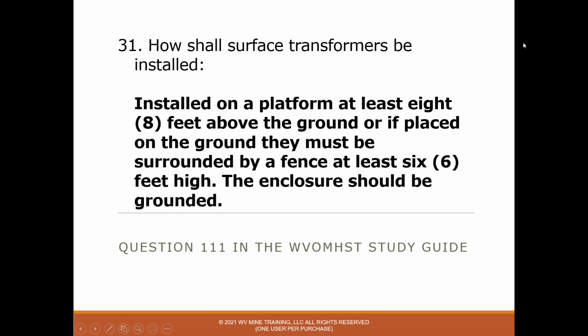Someone's told me this question is definitely on the test, and what they're looking for is the numbers. So if I have a surface transformer, I basically have a choice. I can put it on a platform that's 8 feet or more above the ground, and that's good. No one can get to it. No one can come in contact with it. If I choose to put it on the ground, and most of them I've seen are on the ground, then what I have to do is put a 6 foot high fence around it to keep people from going into that area. And the enclosure should be grounded if it's metal.